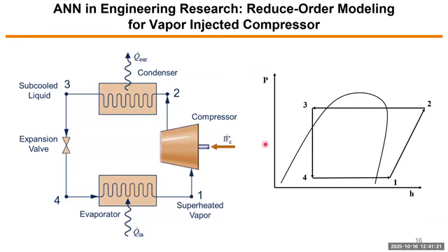But one problem we face with this cycle is when you have a very low ambient temperature in very cold operation, you may have a high pressure ratio, lifting it from 0.1 to 0.2. This results in a very high loss in the compression process, as well as a super high discharge temperature because of friction, and the friction converts into heat, which is carried by the refrigerant to the discharge. Ideally, you do not want too high a discharge temperature—there are issues with reliability and oil degradation.